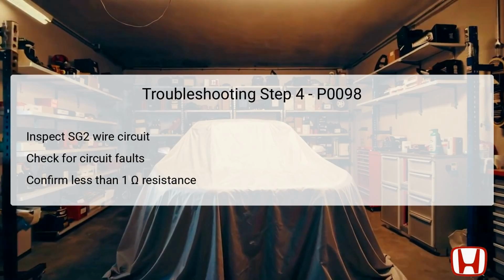Establish a connection to the SG2 line and measure the resistance just like before. It should also read less than 1 ohm to confirm a solid ground connection. This is vital because any integrity issues with the ground circuit could lead to inaccuracies in sensor voltage readings. Should the inspection reveal higher resistance or an open circuit in the SG2 wiring, repairs must be initiated.